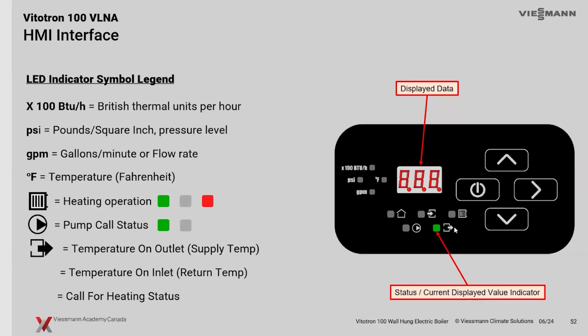The temperature will be displayed on the screen. When you push the navigation button, you see this green LED lit up by the supply out temperature. So this is coming out of the boiler. The other detail here is the supply in, the arrow pointing into the unit itself. When that green LED is lit, we're reading the return temperature. And of course, our call for heat status. If we've got a call for heat, this will be green to let us know that we've got that call for heat.